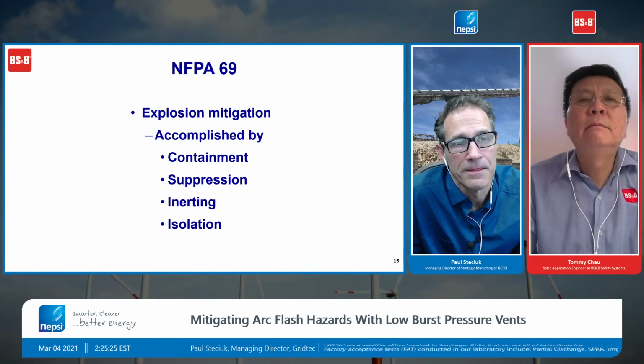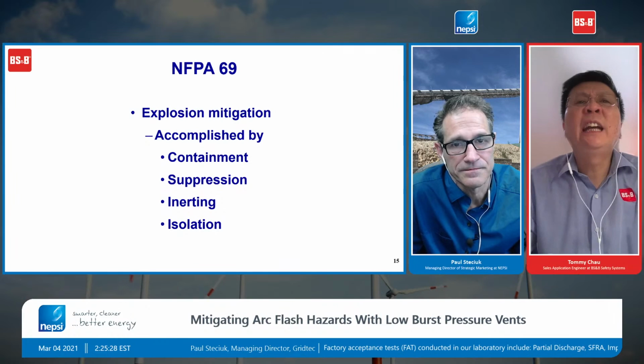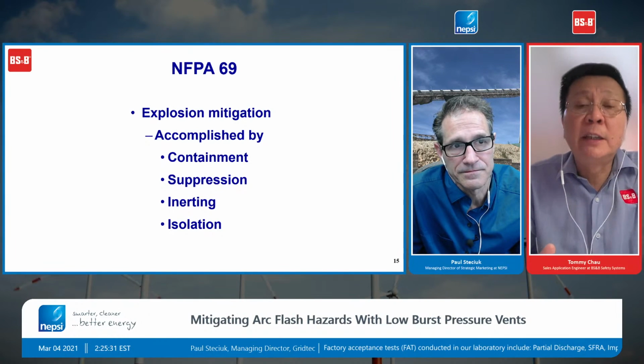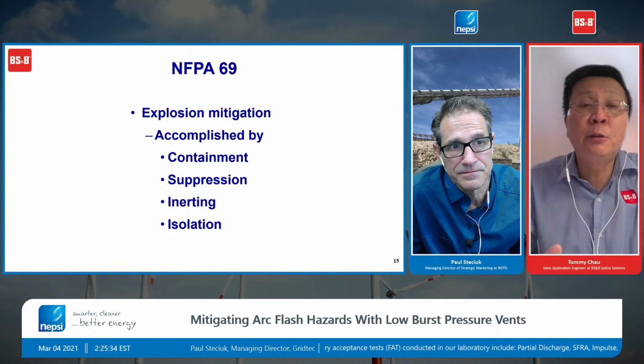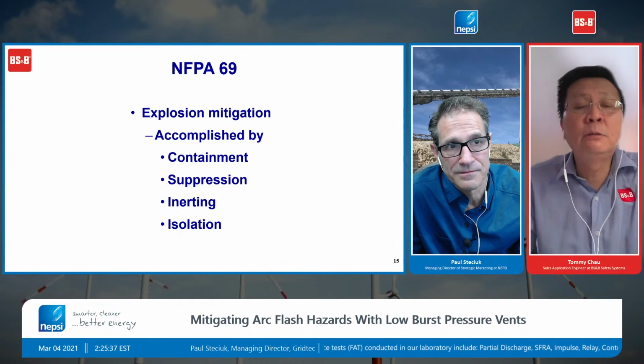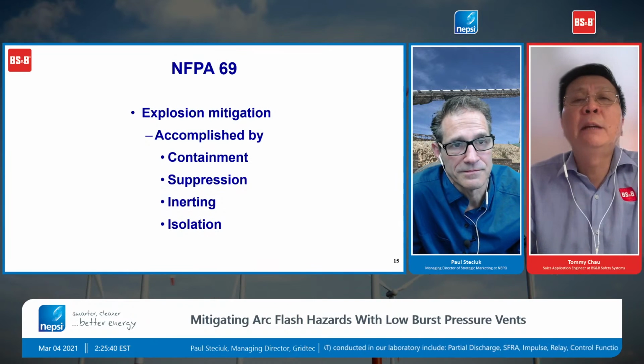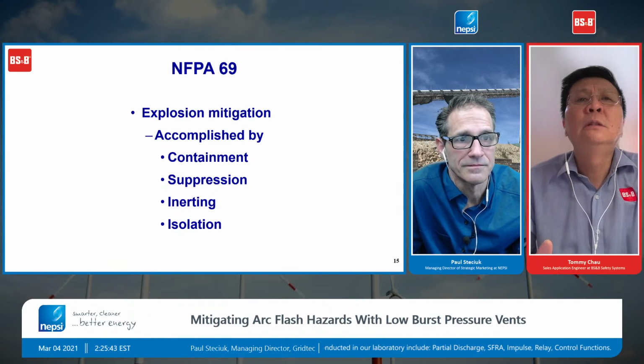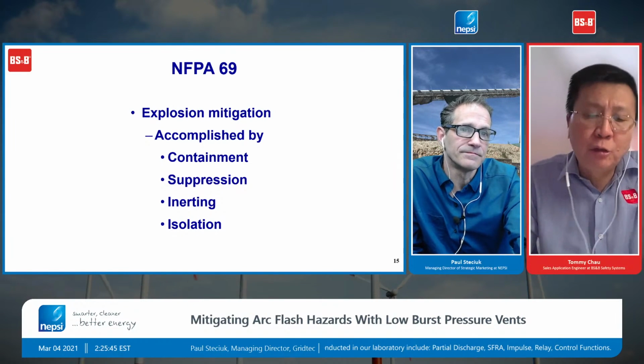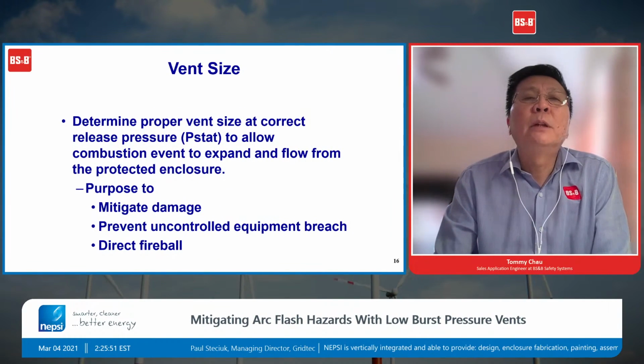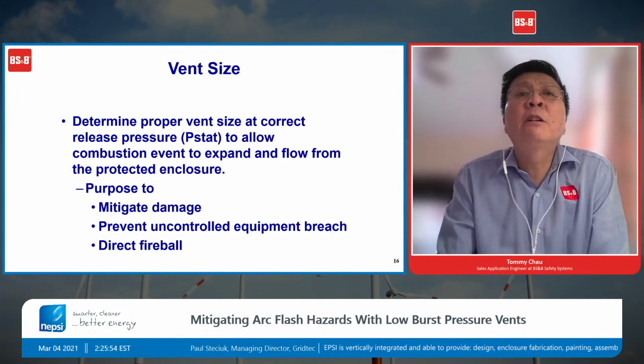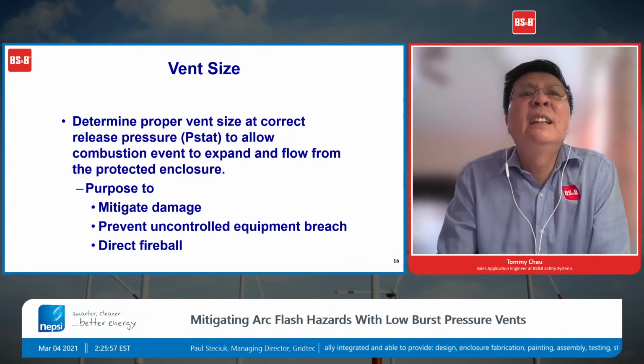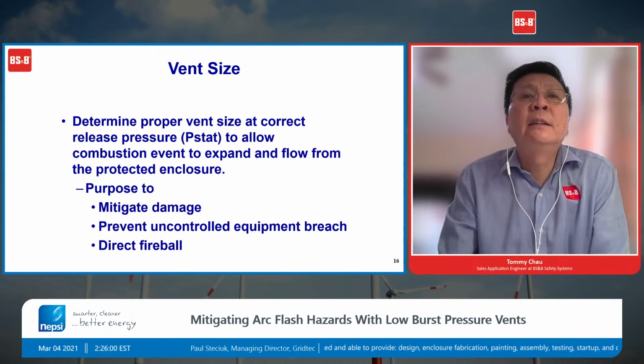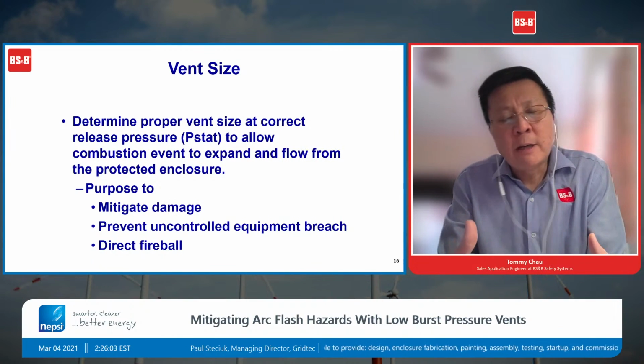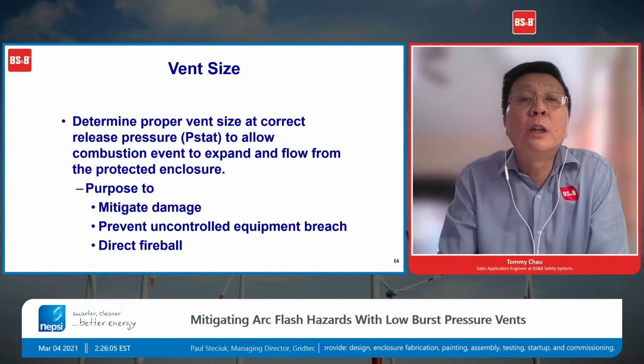Okay, so NFPA 69 gets into what to do if you cannot vent a piece of equipment because it is indoors. Obviously, an explosion vent needs to vent to a safe and isolated area. So NFPA 69 gets into containment, suppression, inerting, and isolation technology. Again, BS&B provides sizing calculations per NFPA 68. The purpose is to direct the fireball and minimize damage to your equipment when using an explosion vent.